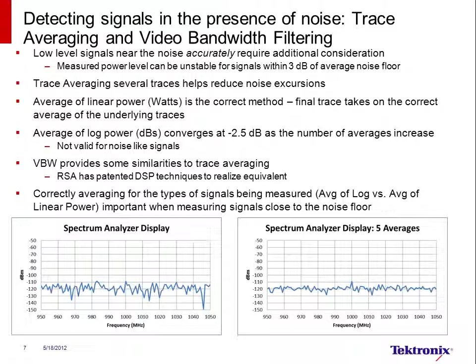Many of today's modern spectrum analyzers are hybrids between analog superheterodyne and digitally implemented analyzers and use fast Fourier transforms, or FFTs, regularly. FFTs are useful as they can help speed up measurements that use analog hardware in legacy spectrum analyzers. The RSA is also an FFT-based instrument, and many signal analyzers on the market use FFTs automatically even in narrowband measurements using a 10 MHz IF signal path. So it's important to understand how the number of FFT points can relate to the RBW used. For this example, we will examine how much a measurement's observed noise floor would increase as a result of the limitation of FFT points for the desired RBW.